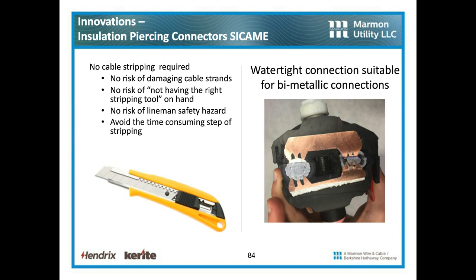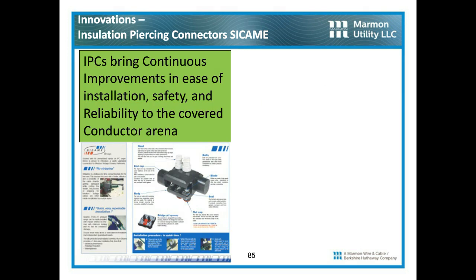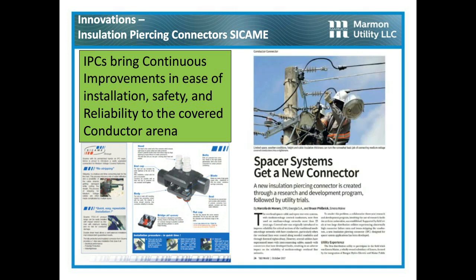Insulation piercing connectors. We've had this at low voltage. This has been around for years, but we've never used it at medium voltage in the U.S. until a couple of years ago. We waited for all the type tests to be passed, and I can tell you personally, I witnessed these type tests, that this is the best thing since sliced bread. There's no cable stripping required, no risk of damaged cable strands, no risk of not having the right tool, no risk of a lineman cutting his hand, and you avoid the time-consuming step of stripping. It's watertight. They're going to bring continuous improvements in the ease of installation, safety, and reliability to the covered conductor arena. And there's a whole bunch of articles out that show you. And we will have information on this ourselves.